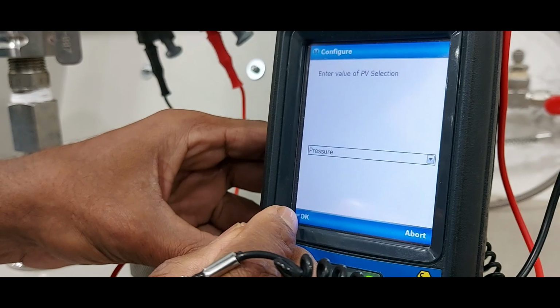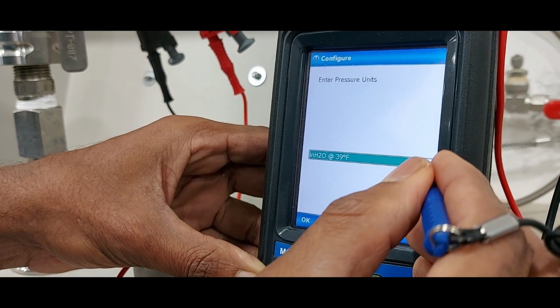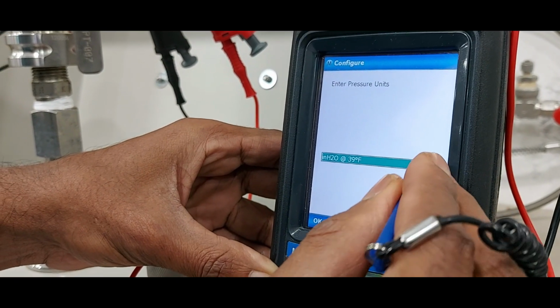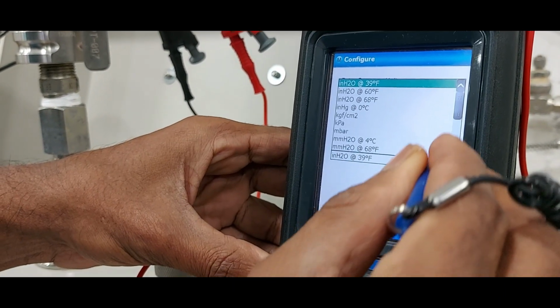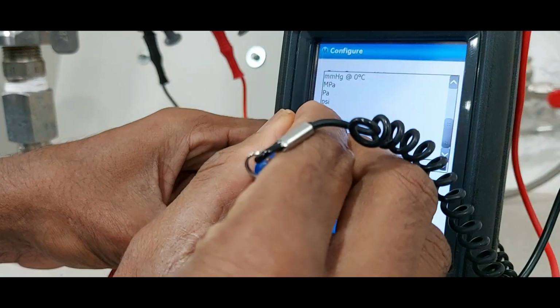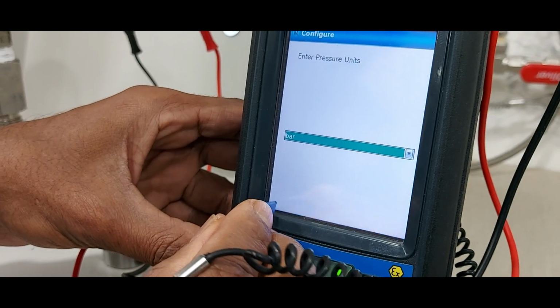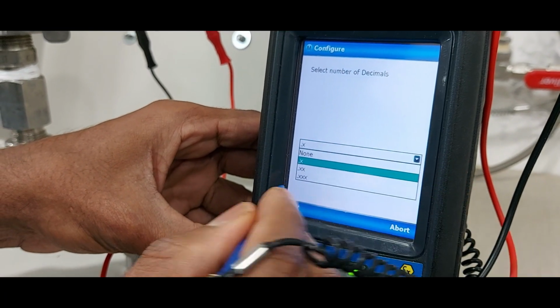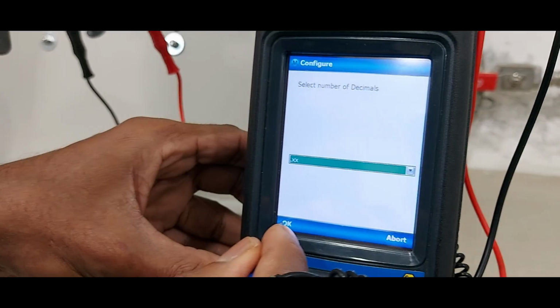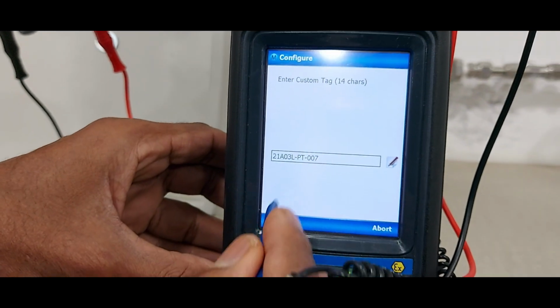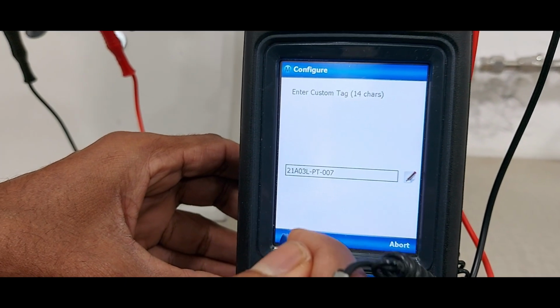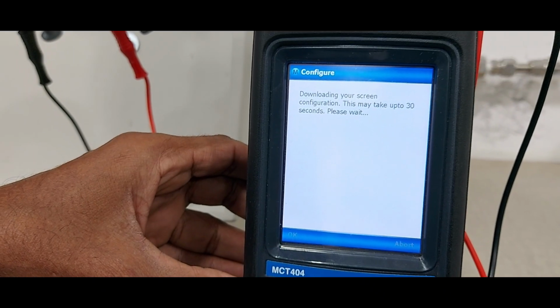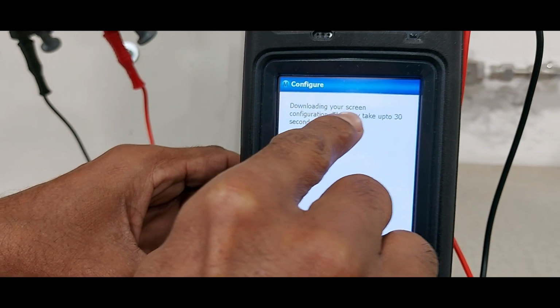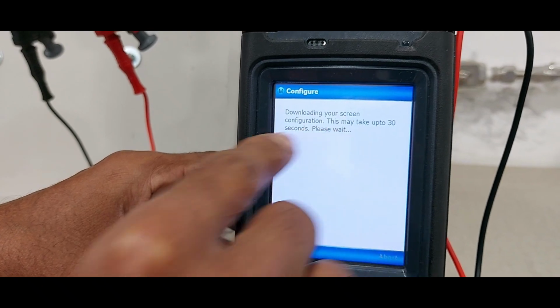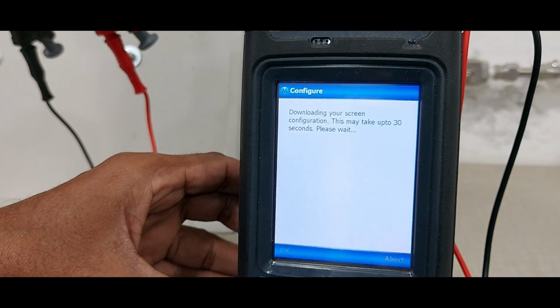PV selection, that is pressure, already selected. We are selecting the next unit, pressure unit. Then OK. Decimal point, we are selecting the 2 decimal point. Then OK. Selecting the tag number is corrected. OK. Then OK. Now downloading the screen configuration. Wait for 30 seconds.